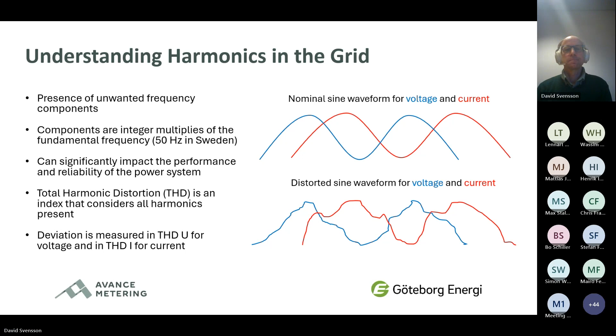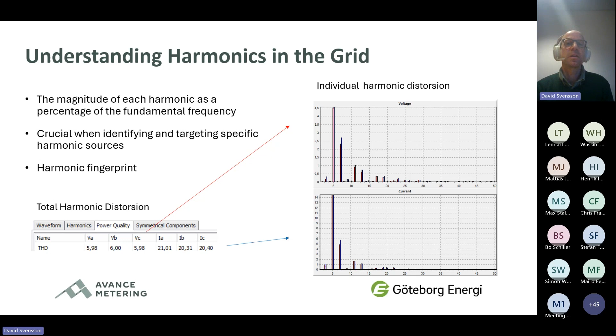Harmonic components can also be measured individually, and we display each harmonic component as a percentage of the fundamental frequency. Individual harmonics can help reveal the source, as different equipment might have a problem with specific frequencies. One piece of equipment can give a fingerprint that might show up in other locations in the grid.